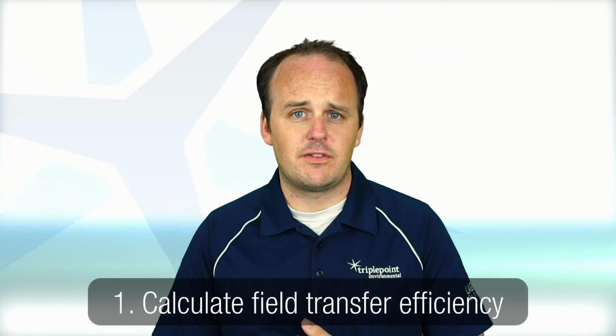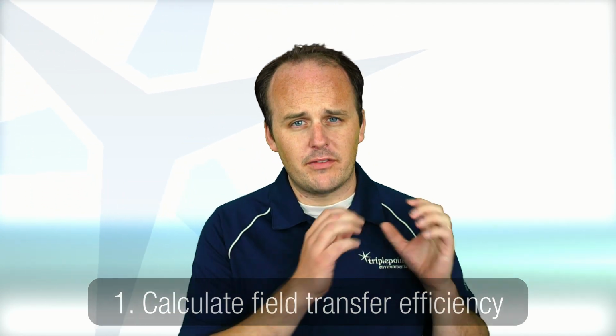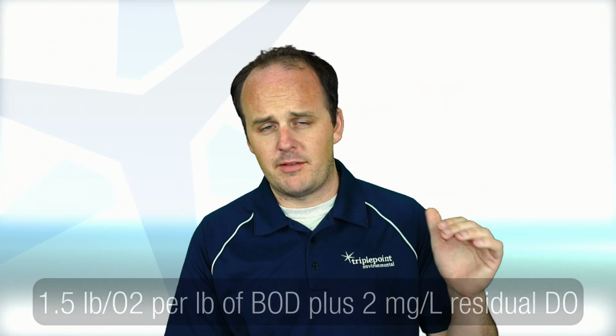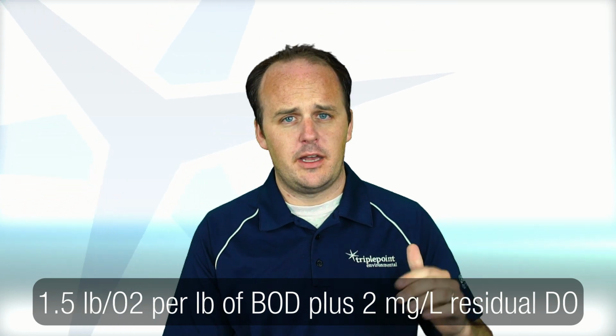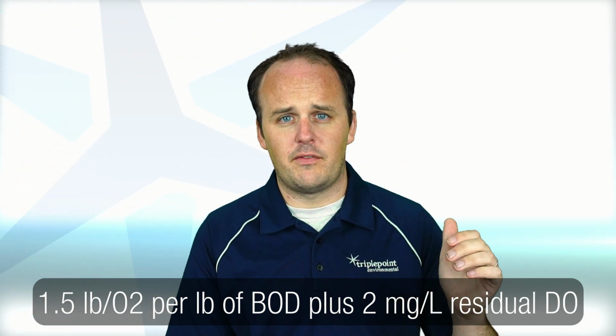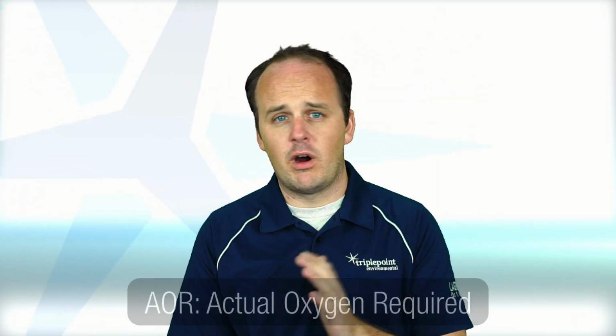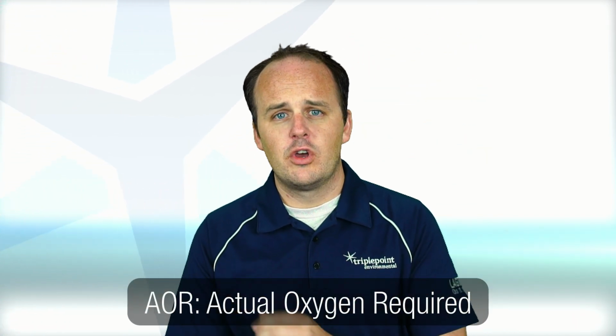So we use two calculations when we're determining the level of treatment through a lagoon. First of all, we need to calculate the field transfer efficiency. Of the amount of oxygen that we need to put in the water in order to break down the waste, which is typically 1.5 pounds of oxygen per pound of BOD, and 2 milligrams per liter of additional residual dissolved oxygen, we get what we call our AOR, or actual oxygen required. How does that translate from our lab clean water testing numbers into the field? That's what the field transfer equation accomplishes for us.